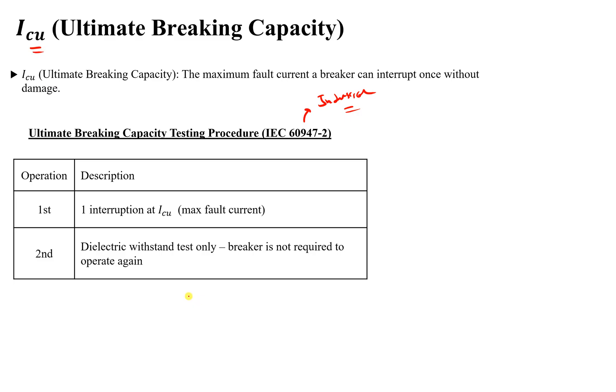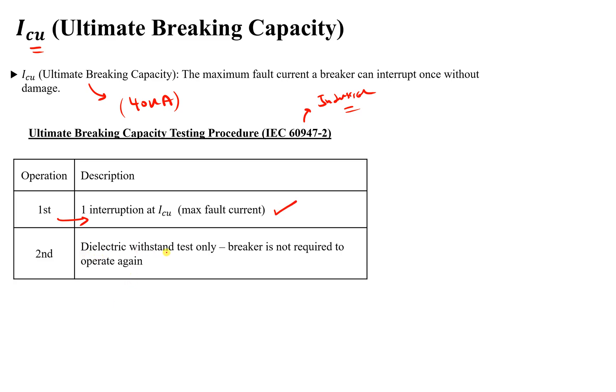The first step is one interruption at ICU. For example, if the ICU is 40 kilo-ampere for a circuit breaker, then we apply a 40 kilo-ampere short circuit to our circuit breaker as a test. After this test, our breaker will not be operated again, but it will not be damaged. The second test is a dielectric withstand test, meaning we apply an overvoltage on the breaker.